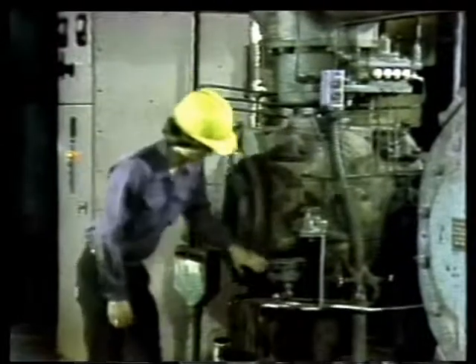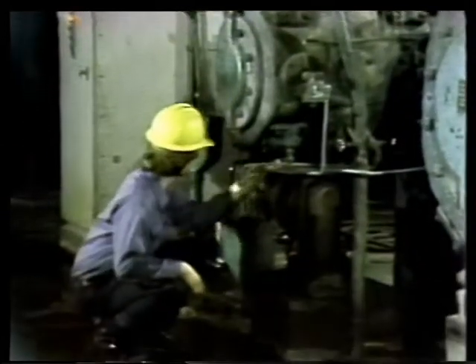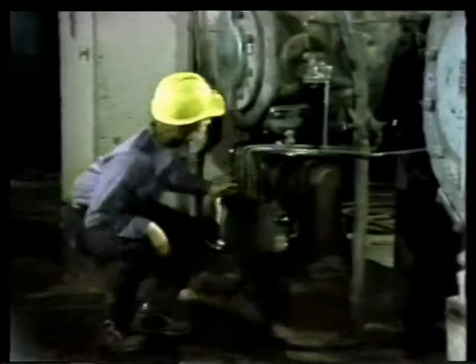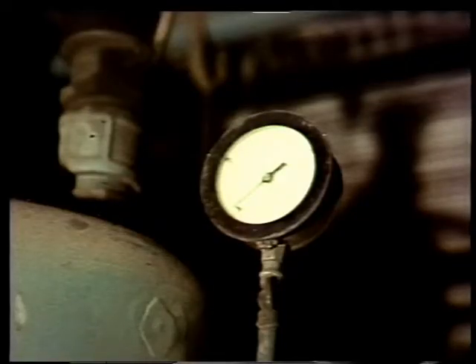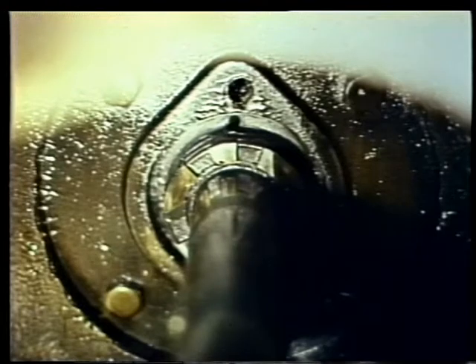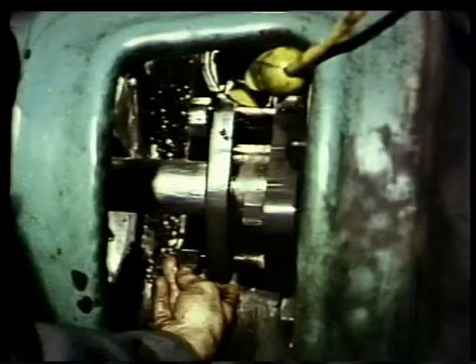But there are still some important jobs to attend to. First, you have to check the operation of the compressor after the tags have been cleared by the proper personnel. Listening and feeling for leaks coming from gaskets, valves, and piping connections is the first thing you should do. You also need to check the discharge pressure and compare it to the figures in the manufacturer's manual and the operator's logbook. The oil wipers are checked to make sure that no oil is leaking out around the piston rod.